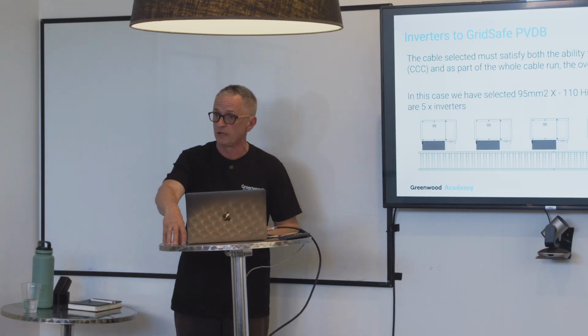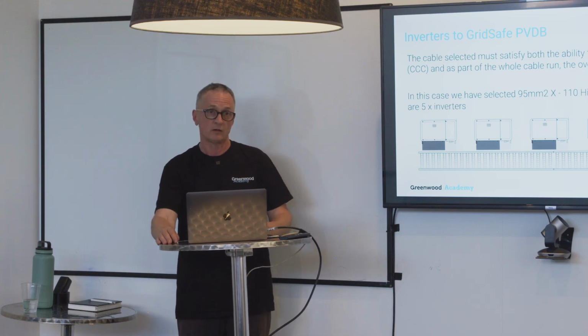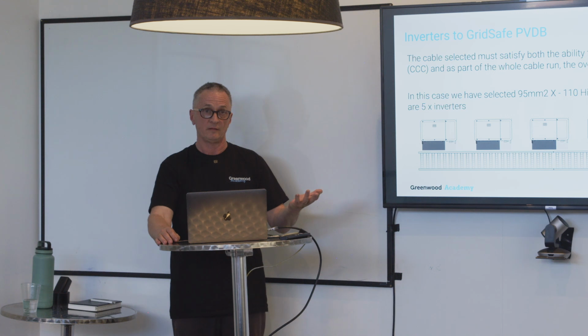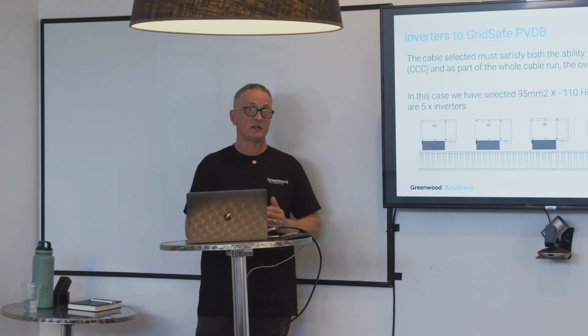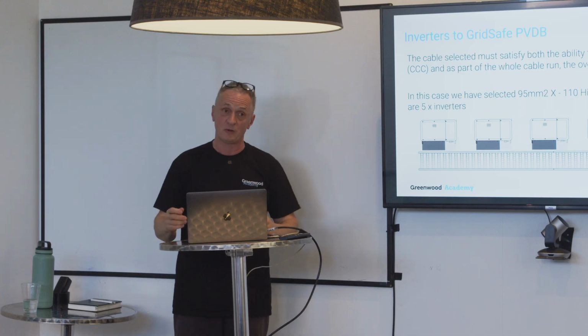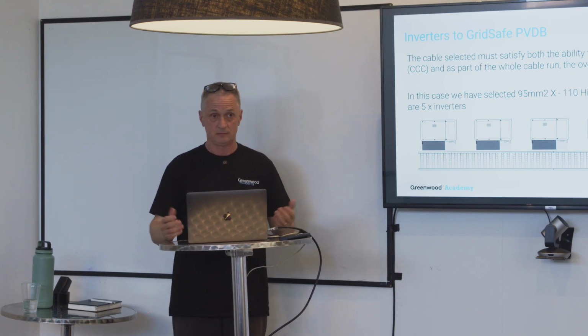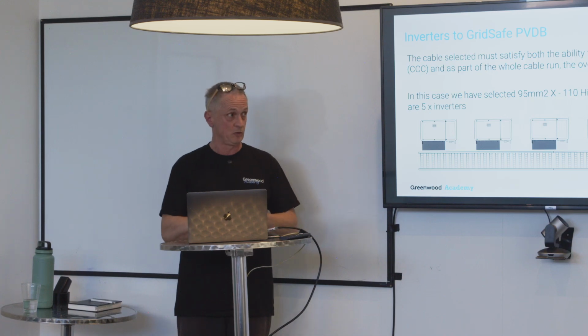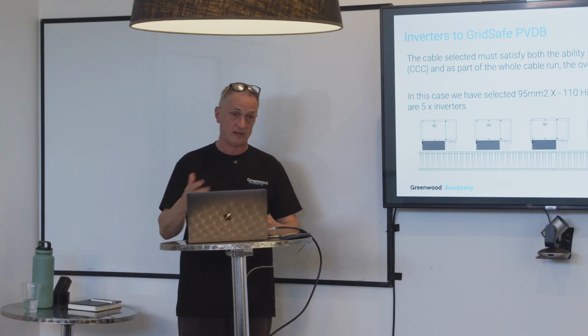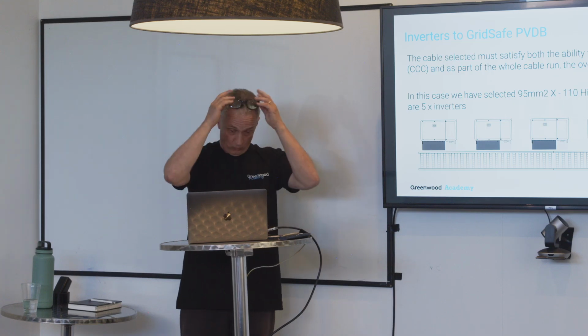And you go, hang on, you've got a lid there, and you're against the wall, and suddenly your cable cannot cope with the capacity that's required because it's been derated. It can be a really interesting conversation, especially when they've already committed and bought cable. But as long as they can prove the calculations abide by AS/NZS 3008 and they're correct and accurate, all should be good.